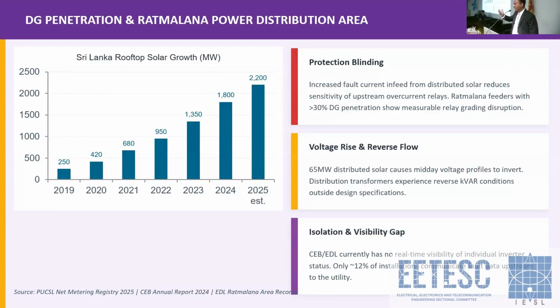So there are a lot of developments, and maybe our engineers would think of these things and implement new models for these protection requirements. And there are reverse power flows. Because of the reverse power flows, our transformers are experiencing power pumping to the high voltage side, which the distribution transformers are not designed for. So a high rate of degradation would be there in distribution transformers.